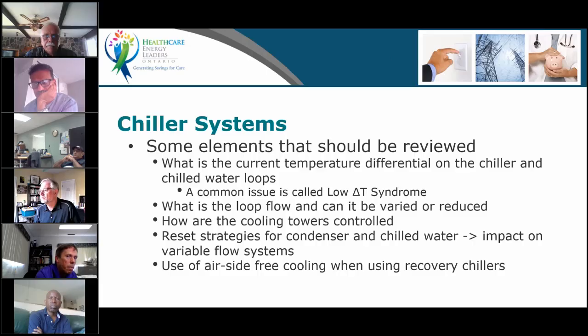I've been in buildings, not necessarily hospitals, where you also check the delta T on your cooling towers, where the delta T was very low and the pump used to be throttled. And somebody saw the throttling and said, hey, that's bad, it's throttled. So they opened it up, because they thought throttling is inefficient. Well, throttling is inefficient compared to a VFD, but opening up a throttle valve is really, really inefficient. So always be on the lookout for your delta T's.